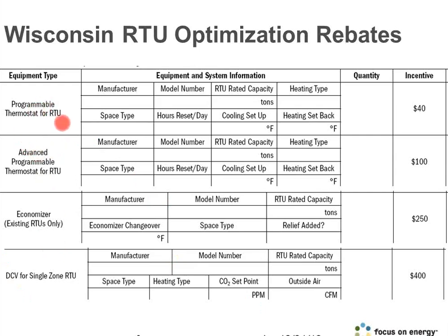One is add a programmable stat for $40. One is add an advanced programmable stat for $100. Basically, that's going to involve some extra wires to shut the outside air louver at night. Because if you didn't know it, rooftop units, every single night when they turn on heating and cooling, even though no one's there, they go to minimum ventilation position, which is obviously a huge energy waster when nobody's there. You don't need ventilation. So this kind of stat will stop that from happening. There's an entire list of approved stats I can send you if you're interested in that. You can add an economizer to one of the existing rooftops that you're tuning up for $250, and you could add a CO2 sensor for $400.